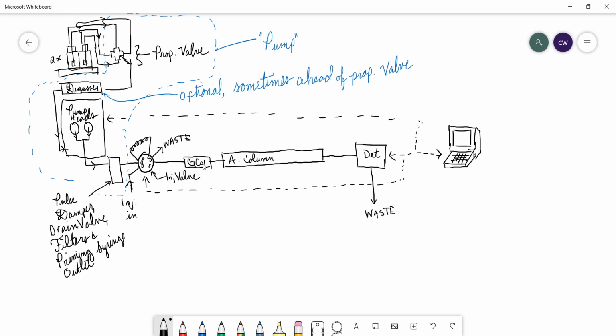After the injection valve, you see the guard column, typically in HPLC systems, and this is, just as it was in GC systems, meant to prevent things that would otherwise damage the analytical column from reaching the analytical column. Okay? It is considered a consumable device. It is sacrificial. These are typically on the order of 5 centimeters in length, as opposed to the analytical columns, which are typically 25 centimeters in length. And when you have just this guard column on line, you should not see a huge amount of back pressure because these are fairly wide bore. Whereas the analytical columns are typically much more narrow bore, they're longer, and they will generate significant back pressure. Okay, back pressures at minimum of around 900 psi are common.